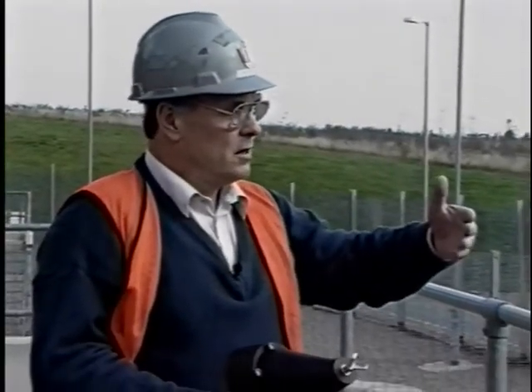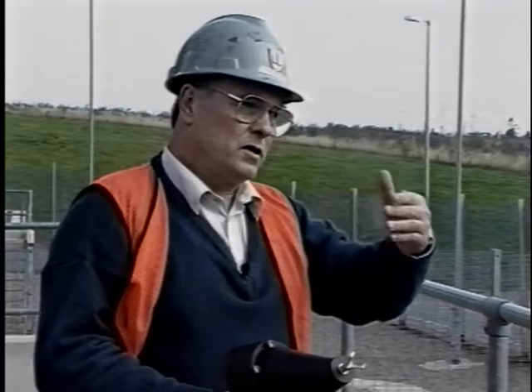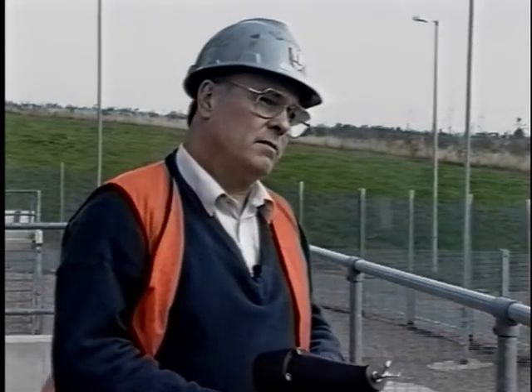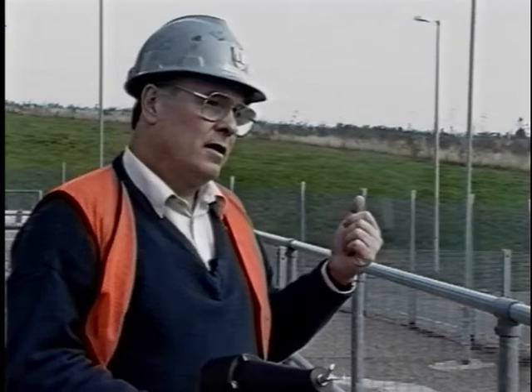The reason for that is for any induced voltage that may come from the rest of the system. If you're working on that particular section, so we don't disturb too much the normal running of the trains, we would re-energise the rest of the system while you're working on that section. And obviously because you've got parallel lines running with the isolated section, there's a possibility of pickup. So the reason for putting the earths on is to stop any induced voltage within that.